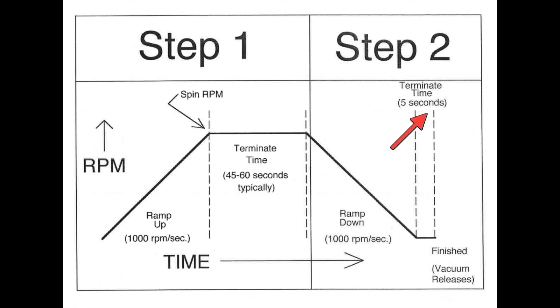So since someone may have entered three or four steps on recipe eight or nine, the one that you're changing, and you might only be entering a two step process, you would need to check steps three and four to make sure zero is entered for the RPMs and terminate times for any steps that follow your recipe.